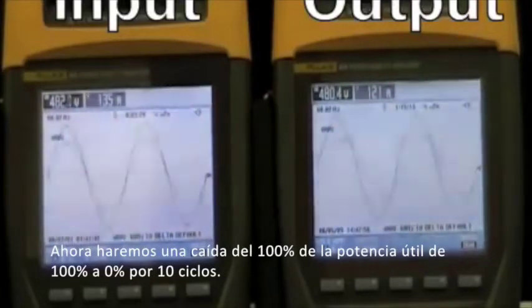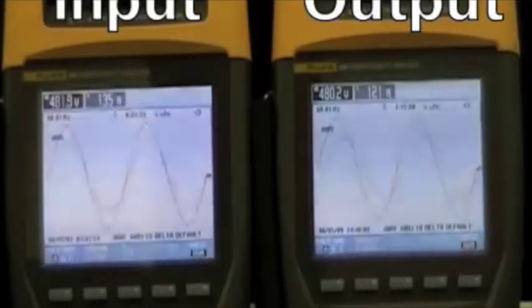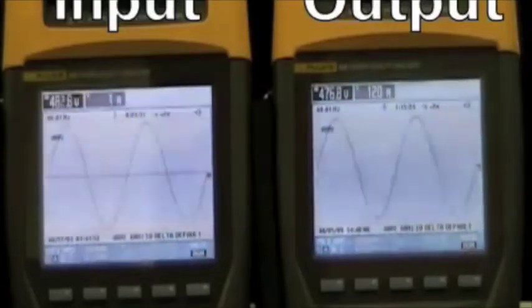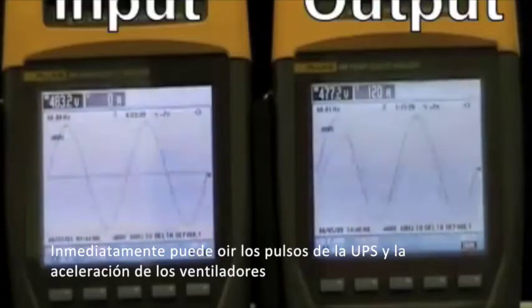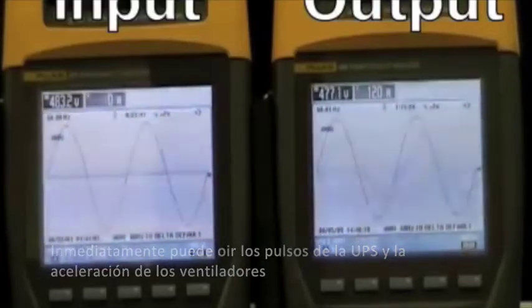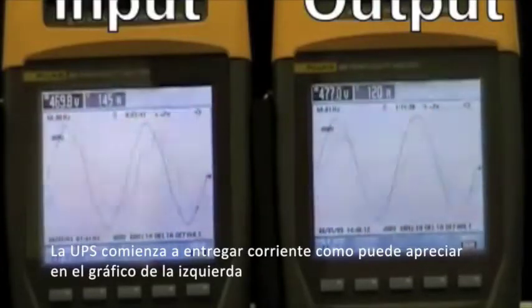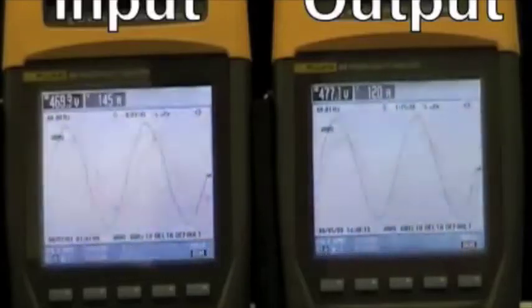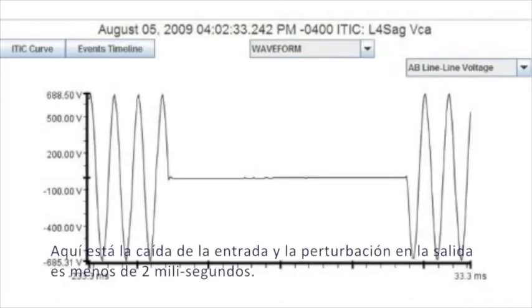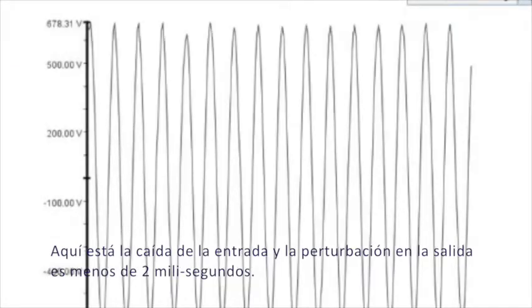And now we'll do a 100% sag of the utility power, go from 100% to 0% for 10 cycles. Immediately you hear the pulse width modulation from the UPS and the fans spin up. The UPS begins to draw input current, as you can see from the waveform on the left. Here's the input sag waveform capture. And the disturbance on the output is less than 2 milliseconds.